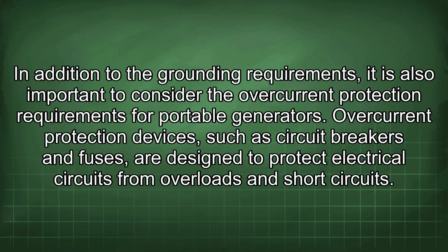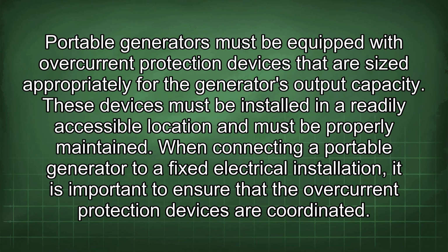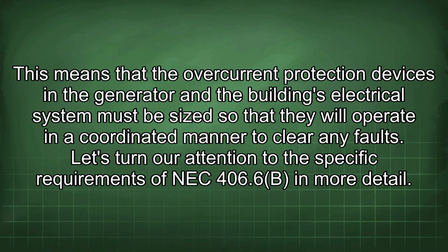In addition to the grounding requirements, it is also important to consider the overcurrent protection requirements for portable generators. Overcurrent protection devices, such as circuit breakers and fuses, are designed to protect electrical circuits from overloads and short circuits. Portable generators must be equipped with overcurrent protection devices that are sized appropriately for the generator's output capacity. These devices must be installed in a readily accessible location and must be properly maintained. When connecting a portable generator to a fixed electrical installation, it is important to ensure that the overcurrent protection devices are coordinated. This means that the overcurrent protection devices in the generator and the building's electrical system must be sized so that they will operate in a coordinated manner to clear any faults.